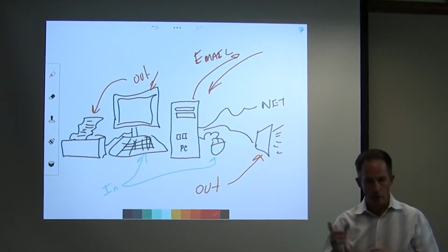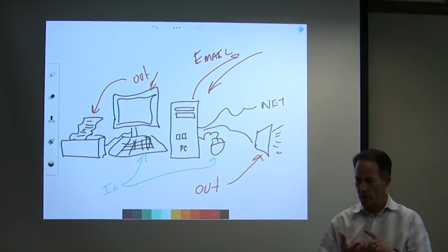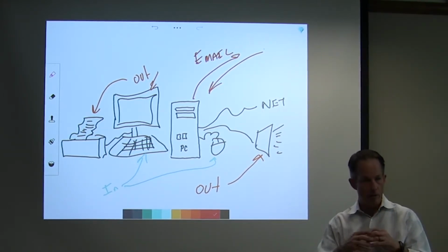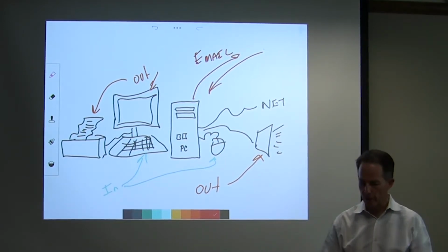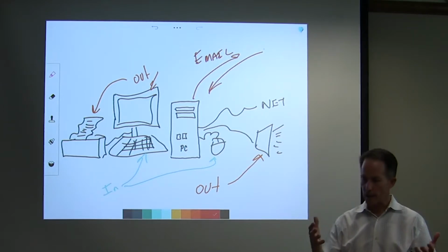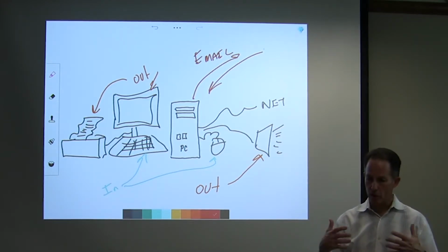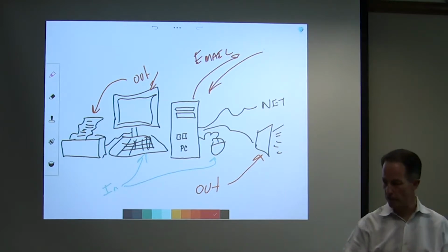Okay. So the supervisor, a couple other things that it benefits us is we have alarming for a global network, for the entire network on campus in one place. The graphics are in one place. Histories are also in one place. It also, if developed correctly, gives us a way to do global updates and changes on the Jaces.